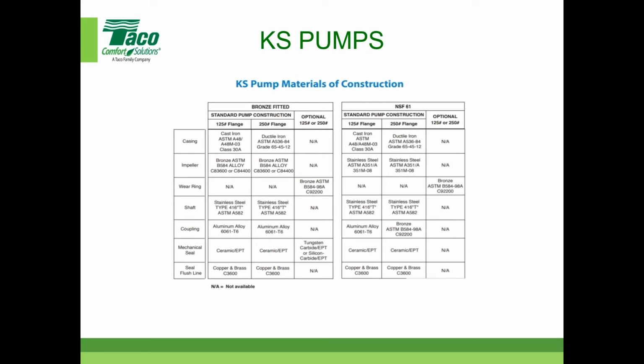It's really the same material breakdown as our FI pumps. Something to consider there: we do have that optional wear ring. As you can see, the impeller is bronze, the casing's cast iron, and that's the actual call out of it there. If you go to 250, it is a ductile iron because it just has to have a little more oomph to it.